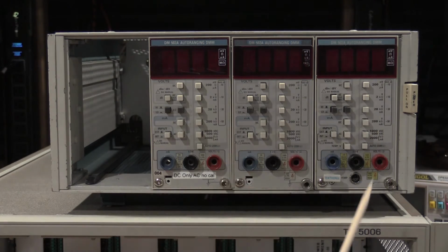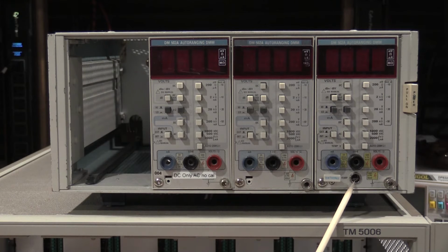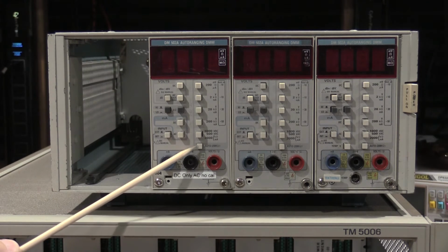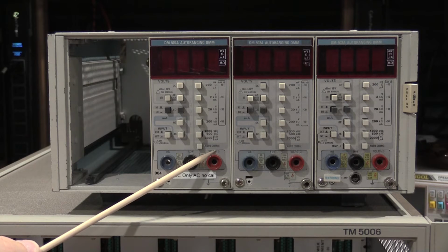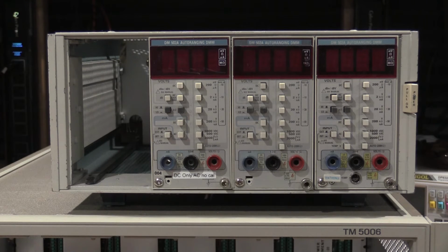Some of the 502As have a temperature probe on them. Some of them don't. Just a thing with the 502As. The other thing to note that's a little weird with the 502s is they have a 20 megohm input. This kind of leads back into most meters have a 10 megohm input impedance. These have a 20 megohm input impedance. Doesn't load the circuit as well. Doesn't work so well with high voltage probes. Just something to be aware of.